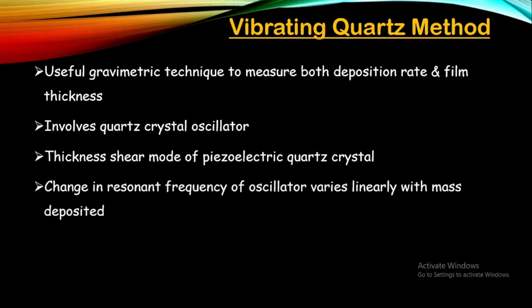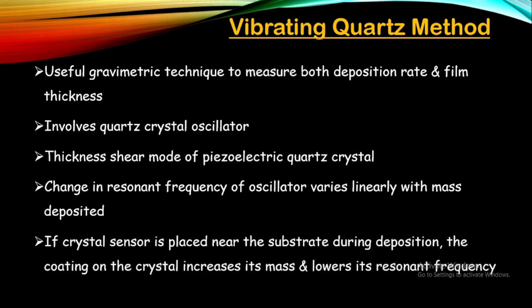The key question is how to measure thickness. The change in resonant frequency of the quartz oscillator during deposition is going to vary linearly with respect to the mass deposited on the crystal electrode. As deposition takes place, the mass varies, and as the mass varies, the resonant frequency of the quartz oscillator varies because a stress acts on the quartz crystal. If the crystal sensor is placed near the substrate, coating on the crystal increases its mass and lowers the resonant frequency — the two are inversely proportional.